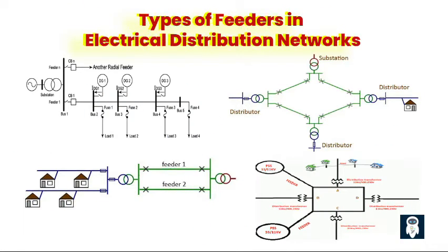There are different types of feeders in the electrical distribution world, each with its own specific role. Some feeders are like the main highways, carrying a large volume of electricity to densely populated areas; others serve remote locations with lower power demands. First, the radial feeder is the simplest and most common type, operating in a radial configuration where power flows from the source to the load points in a single direction. However, a fault in a radial feeder can cause an entire section to lose power.